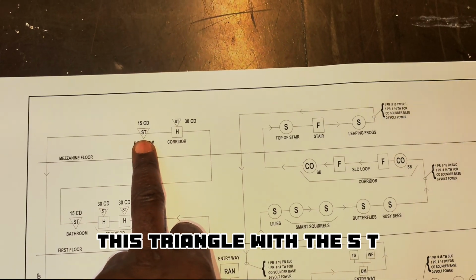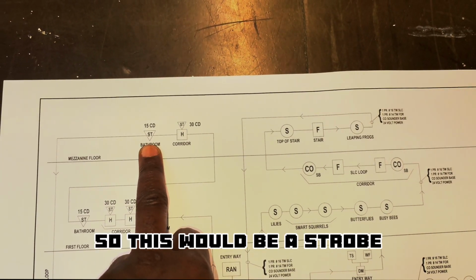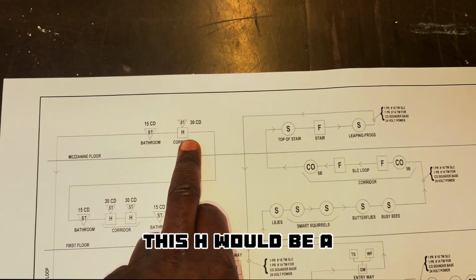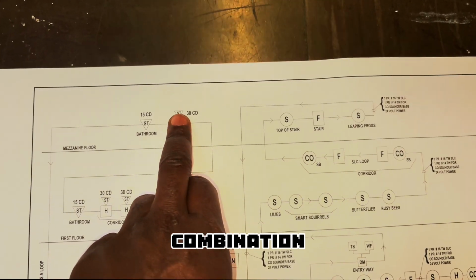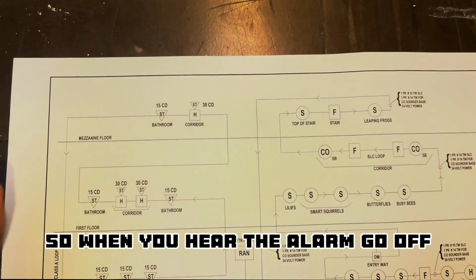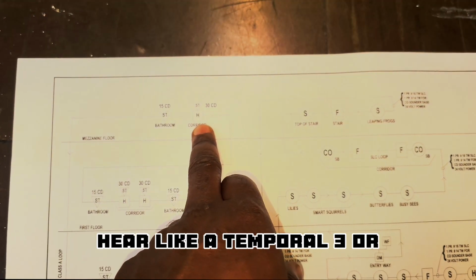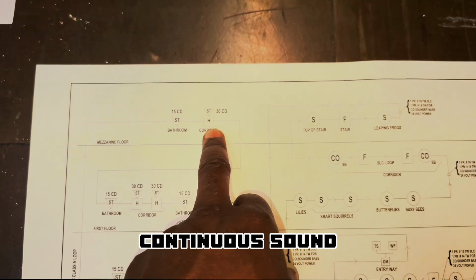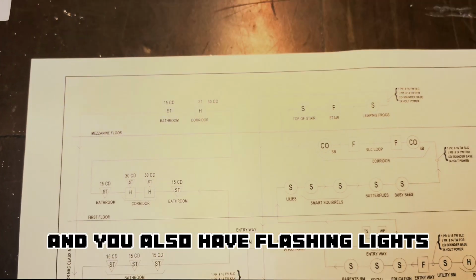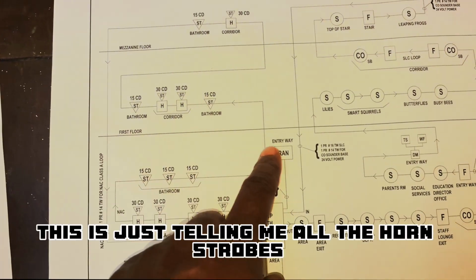This triangle with the ST is just a strobe. So this would be a strobe only, just a flashing light. This H would be a horn strobe. So we'll have a combination horn and strobe. So when you hear the alarm go off, you will sometimes hear a temporal three or continuous sound. You'll hear some type of noise, and you also have flashing lights associated with that. This is just telling me all the horn strobes that need to go on every particular floor.